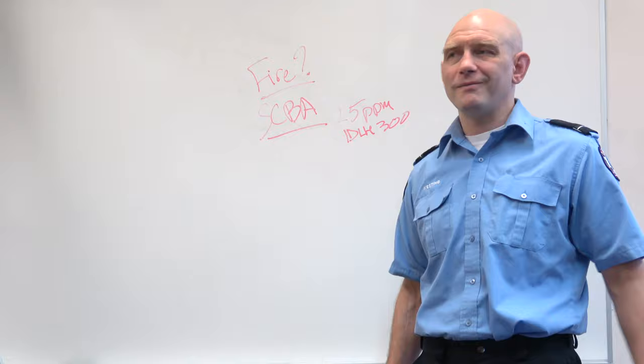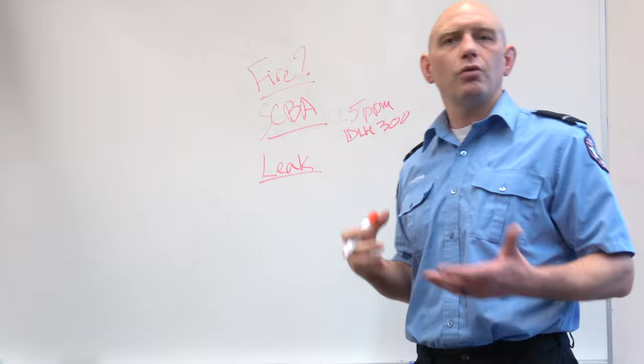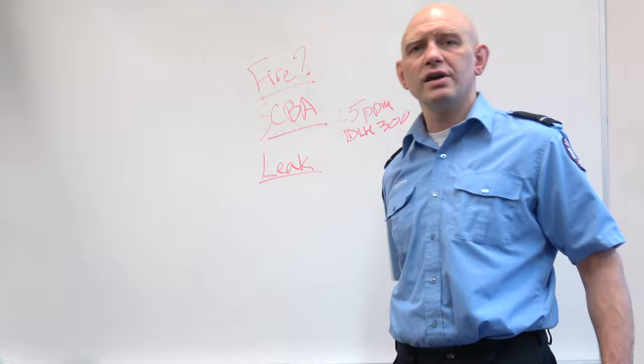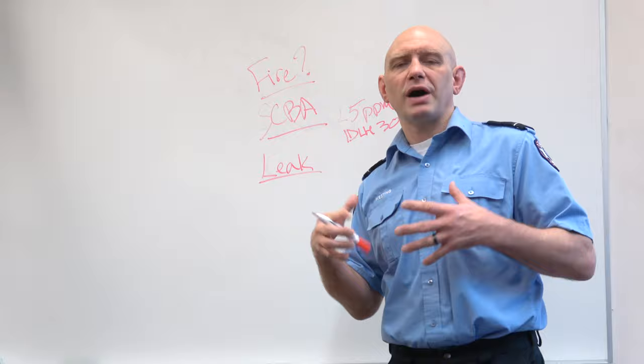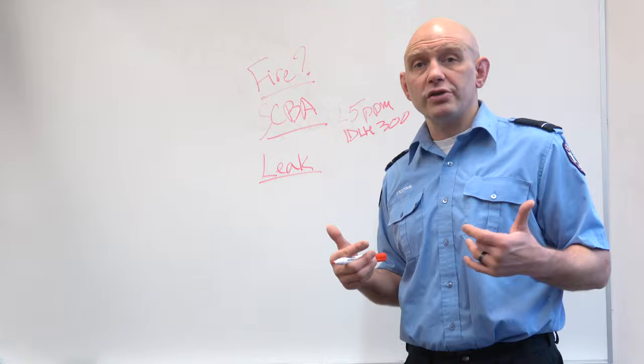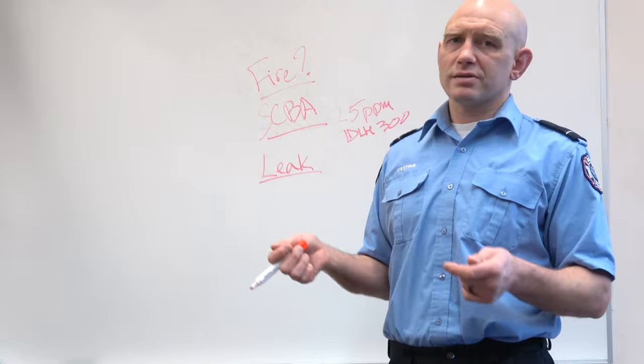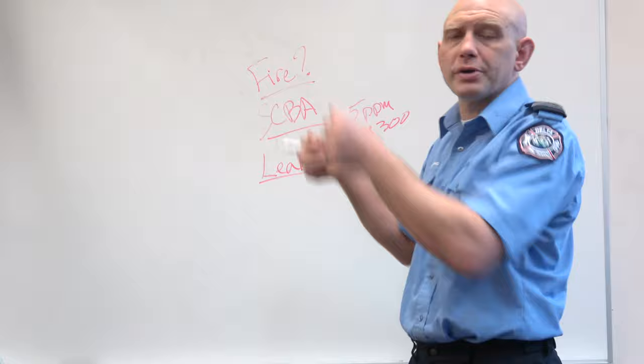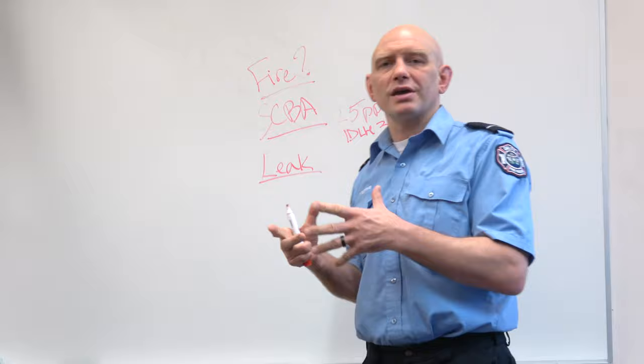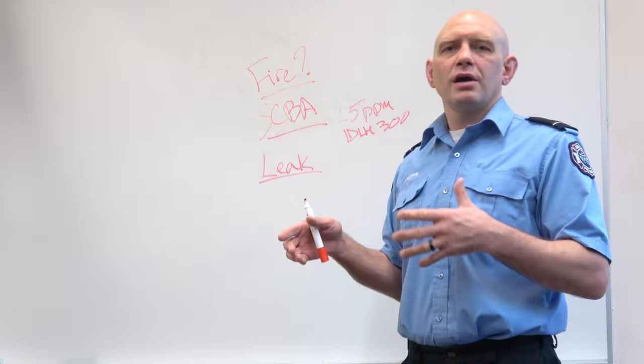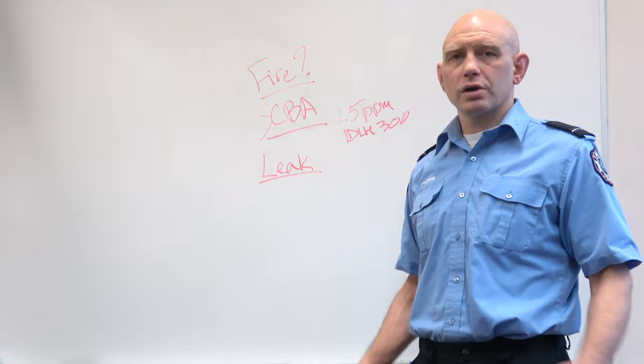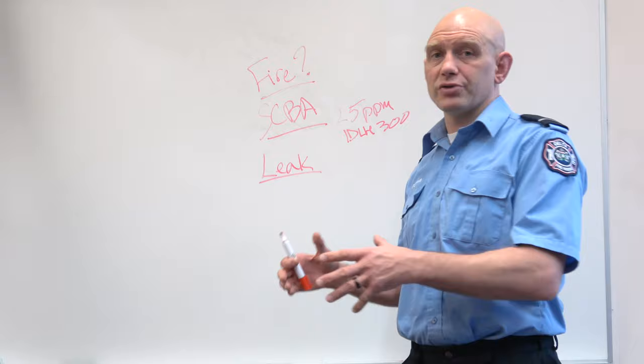You've got to be aware that ammonia techs who are working with this stuff all the time are just going in there in coveralls and maybe a respirator. They're actually outside the bounds of what's allowed by WorkSafe. For ammonia, the threshold limit value is 25 parts per million. The IDLH is 300. You're not allowed to be on a respirator in a 300 parts per million environment. Those guys are going in there 500, 700, 1000, and they're putting up with any wet areas of their body beginning to get burned because the ammonia settles out. So we're typically going to be wearing a higher level of protection than those cowboys.